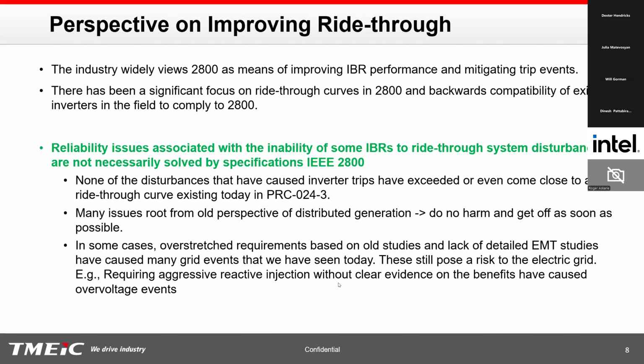A lot of these issues come from the old perspective of inverters not doing any harm to the grid, the age-old saying of do no harm, just get off the grid as soon as possible. The inverters have come a long way since then, and the protection functions have changed over time to meet transmission requirements. The understanding among inverter OEMs, at least from our perspective, has changed. In many cases, we found that some grid requirements have actually caused inverters to trip more than they would have.